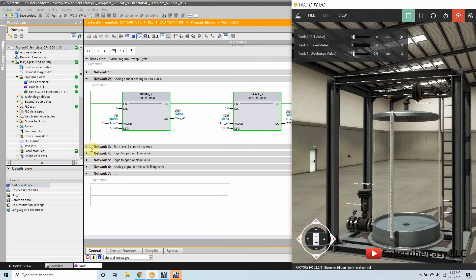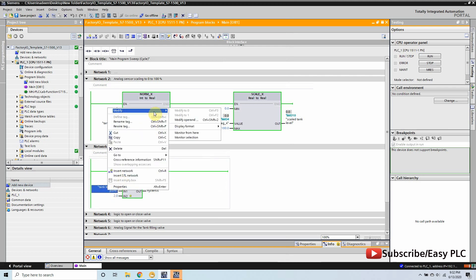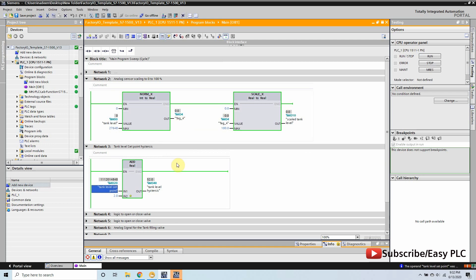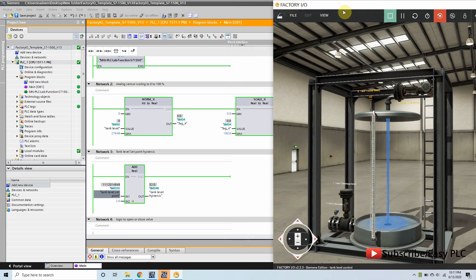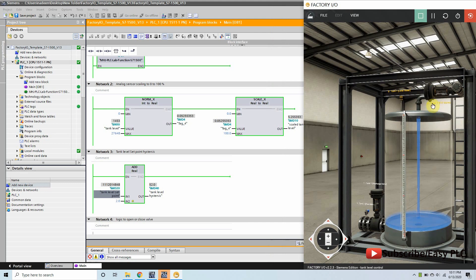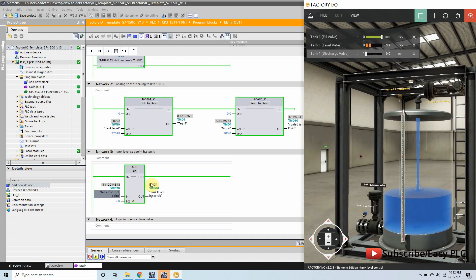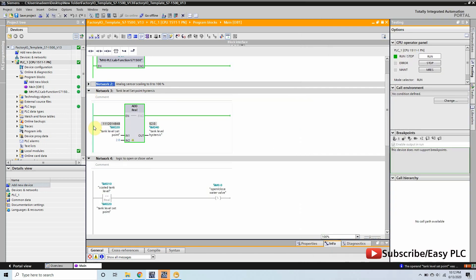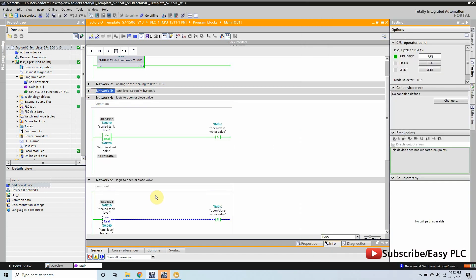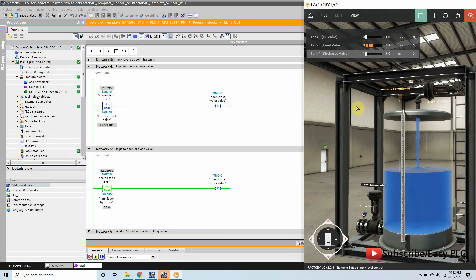You can see that the tank filling valve is still closed because we have not given the setpoint to control the tank level. Let's go and modify the tank setpoint — we will give setpoint 50. This means that the filling valve will open if the tank level is less than or equal to 50 liters, and the filling valve will be closed if the tank level is greater than 52 liters. You can see that the tank level is less than 50 liters, the filling valve opens and starts filling water, and it will stop filling once the level has reached 52 liters. Once the tank level is above 52 liters, it will reset the filling valve with M0.0 and the filling valve will be closed.